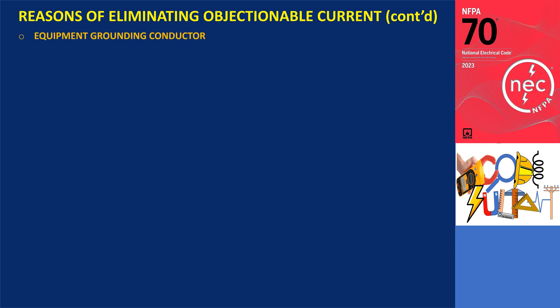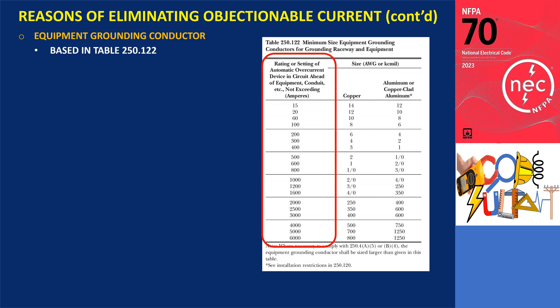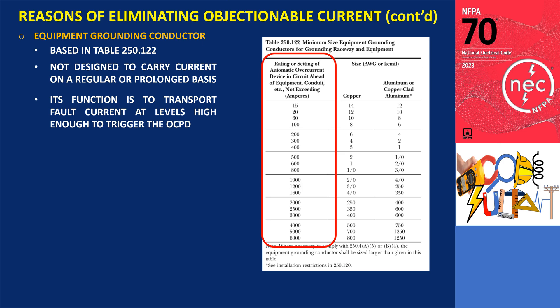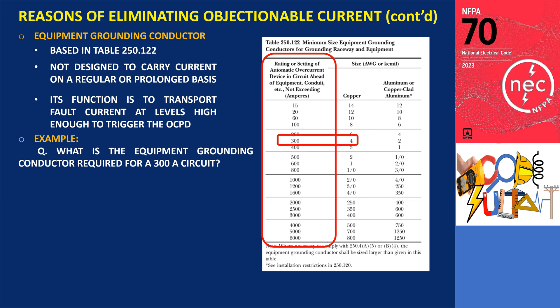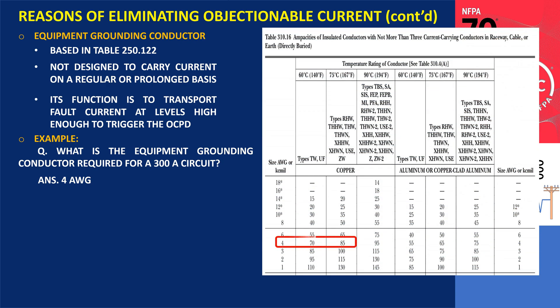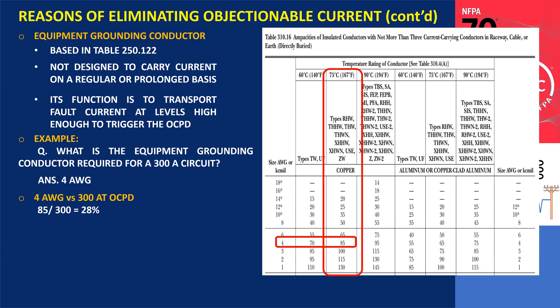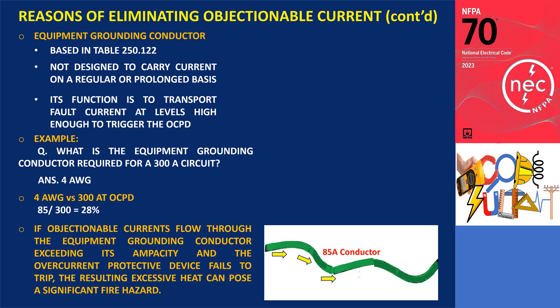Furthermore, the sizing of equipment grounding conductors is primarily determined by Table 250.122, taking into account the characteristics of the overcurrent protective device. Equipment grounding conductors are not intended to carry current under normal circumstances. Their purpose is to carry fault current of sufficient magnitude to activate the overcurrent protective device. For example, Table 250.122 specifies that a minimum 4AWG copper equipment grounding conductor should be installed for a circuit protected by a 300-ampere overcurrent device. However, a 4AWG copper conductor with 75°C rated insulation has an ampacity of only 85 amperes according to Table 310.16, representing just 28% of the overcurrent device rating. If objectionable currents flow through the equipment grounding conductor exceeding its ampacity and the overcurrent protective device fails to trip, the resulting excessive heat can pose a significant fire hazard.